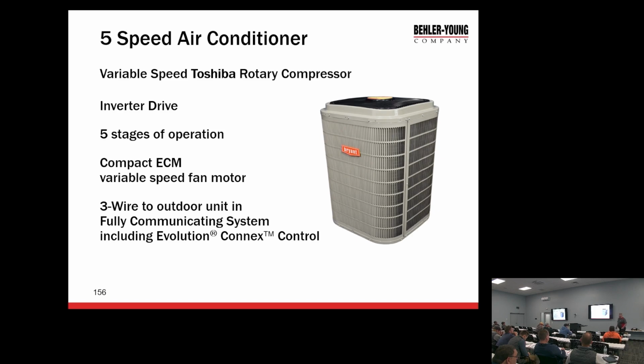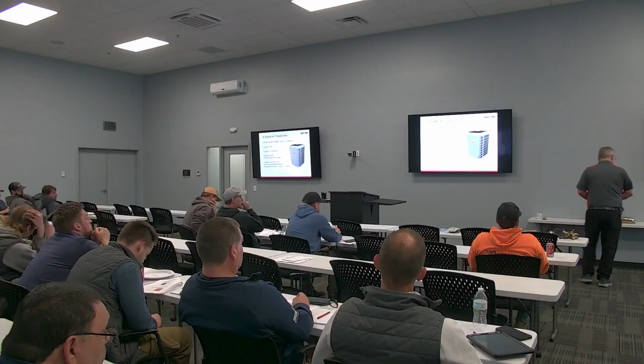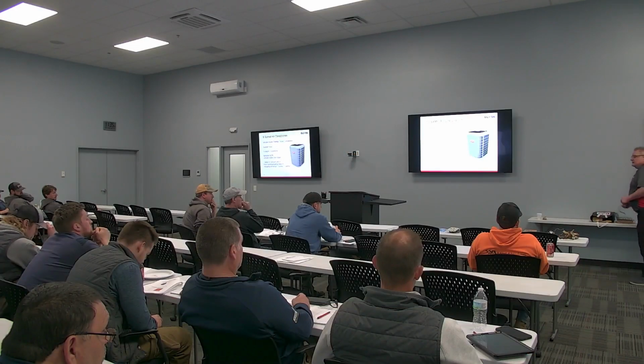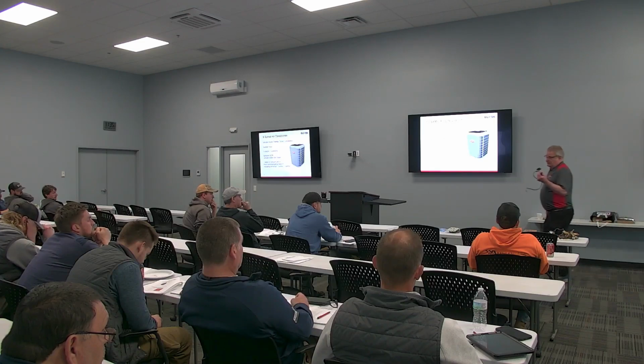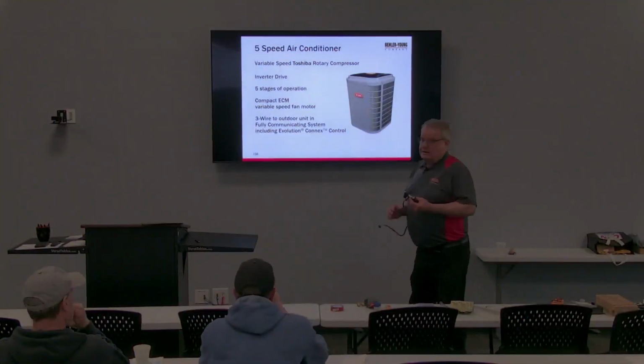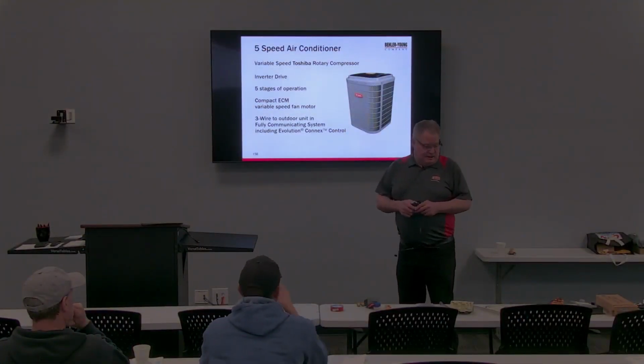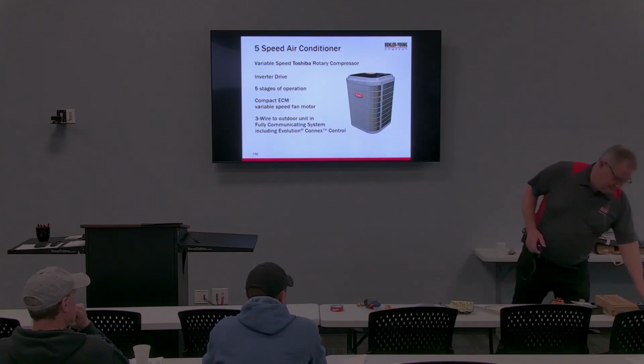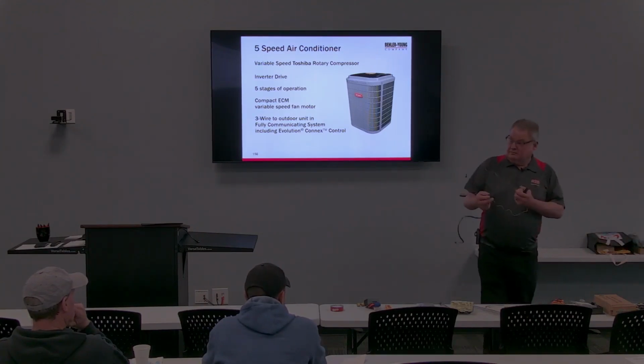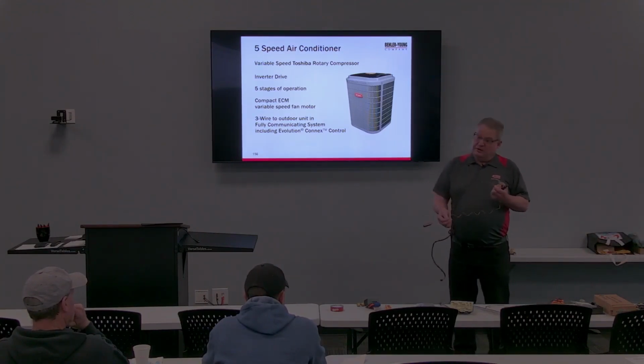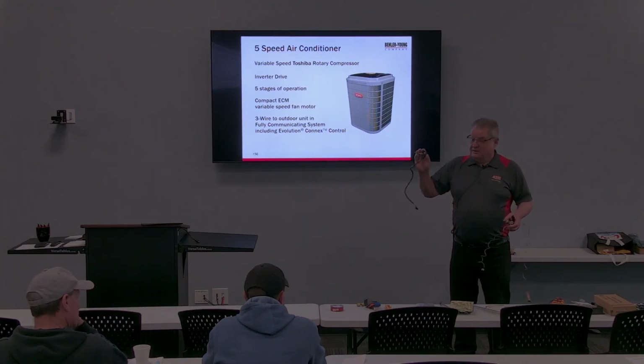Okay, Dave talked about TXVs. These have EXVs, electronic expansion valves. They work exactly the same. The TXV has a sensing bulb on it, right? And it controls and maintains superheat. This has a thermistor on it. Okay, it's not connected directly here, but on the control board somewhere.